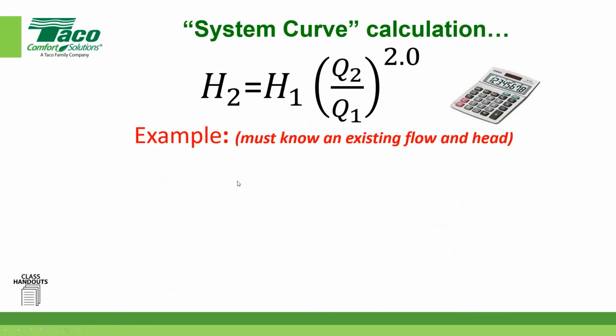That might be an intuitive guess, but in this case, it's not correct. We get into things that are beyond what we really need to go into, pump affinity laws and things like that. But this whole square root thing that I'm showing you, things squared here, gives you a hint of where we're going with that. So this calculation looks like this. We're solving for the new head, which is H2. In order to get that, we must know what H1 is, and we need to know what Q1 is. This is where we got the 20 and 20. The new flow is 30, and the result of that we're going to square and then multiply by the head. This is how I write it out. This is how I like to do it. You can do it any way that makes sense to you.